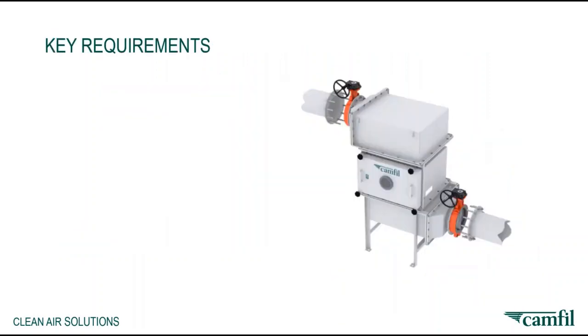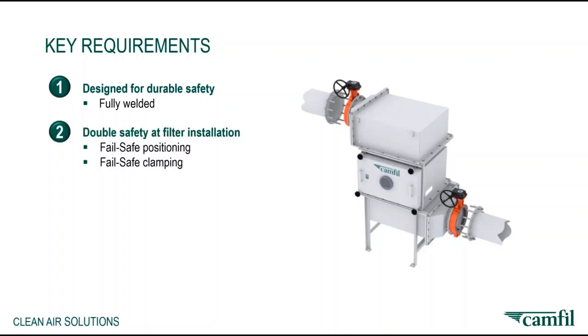Key requirements for such a containment level housing system. Number one, as the name says it, they have to be designed for durable safety, and fully welded on this level is not an option anymore. Number two, they should provide a double safety at filter installation, and we mean a fail-safe filter positioning and also a fail-safe clamping. Number three, they have to be designed for BIBO operation, that is mandatory for operator safety. But it also means every operation has to be possible through a thick plastic bag. And that is why point 2 is so important.